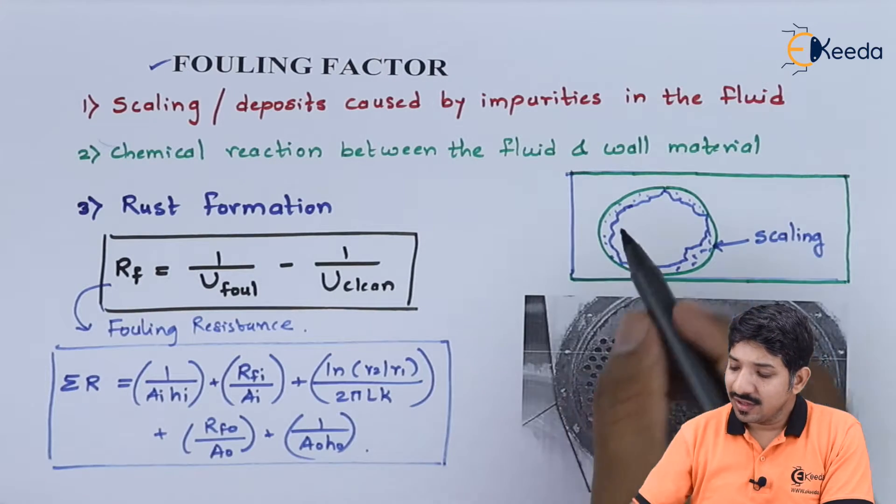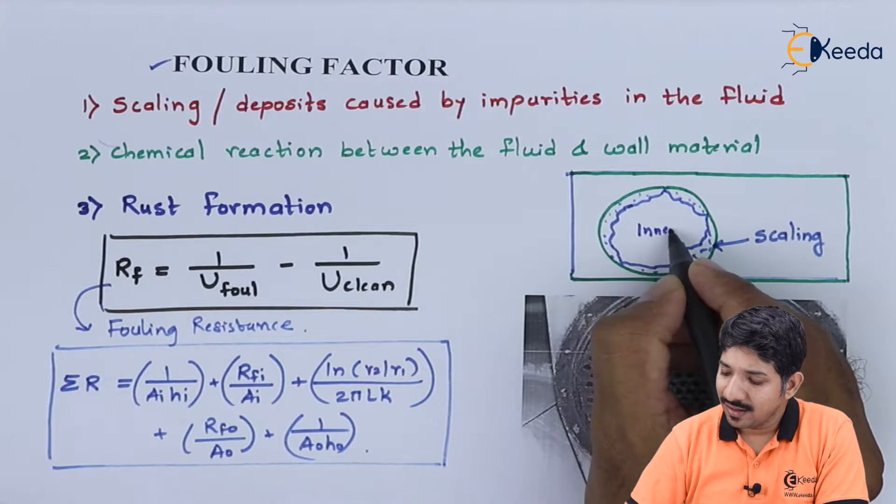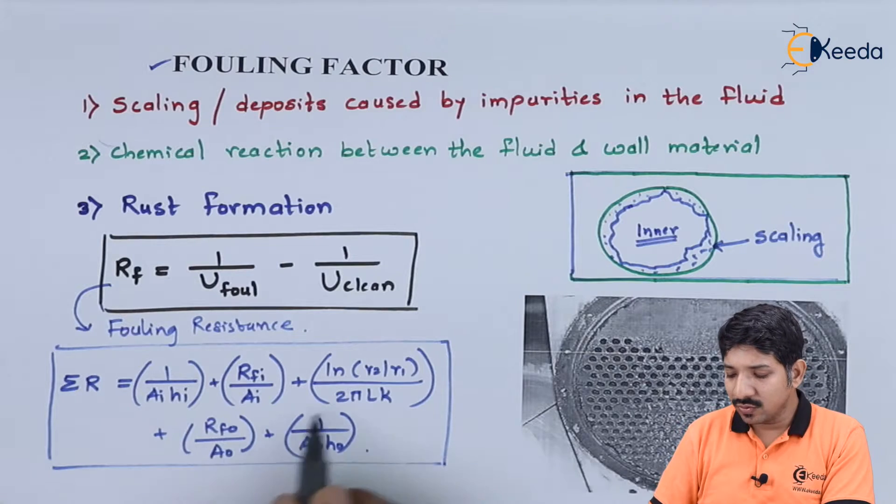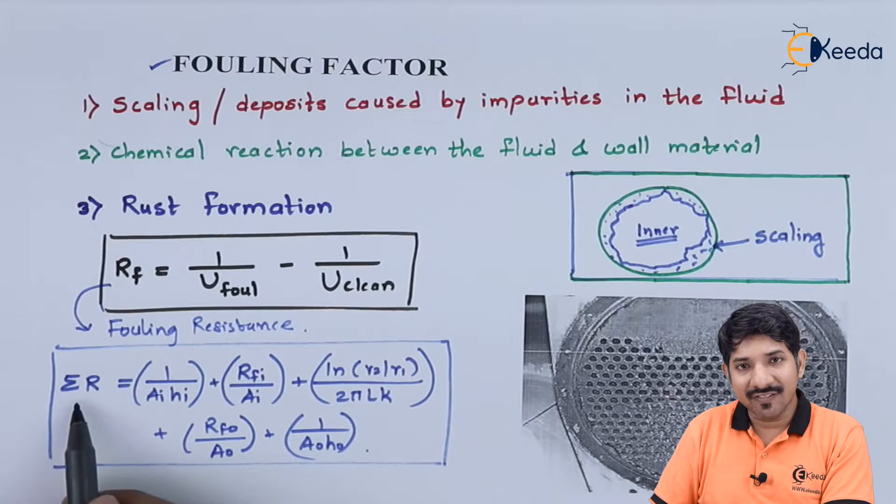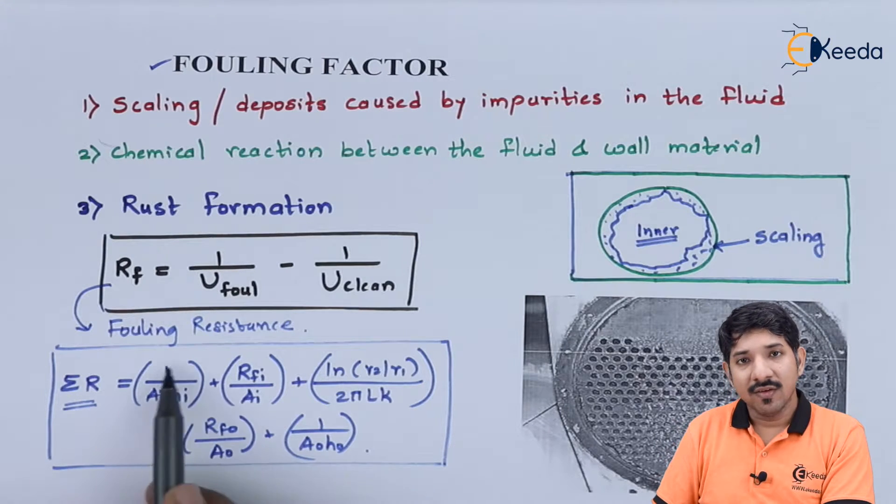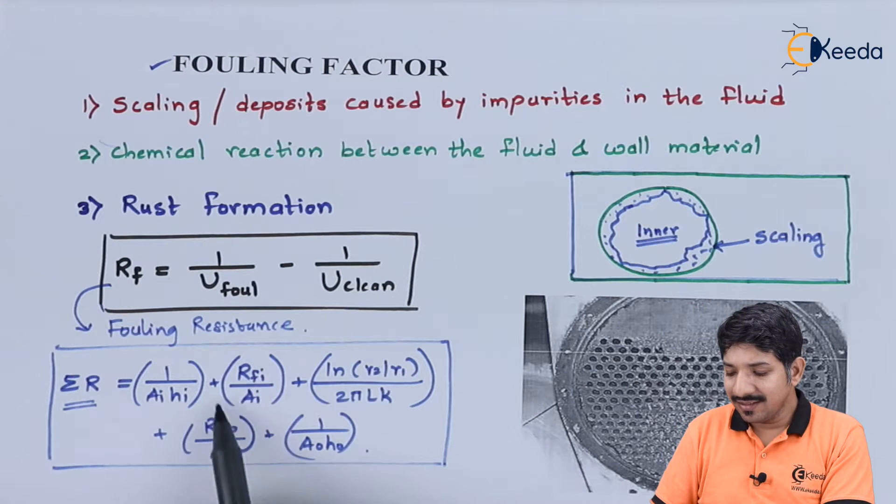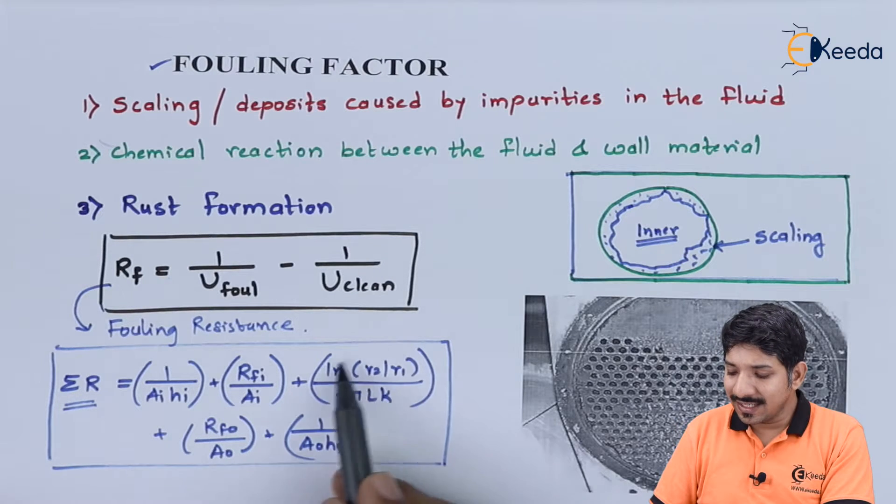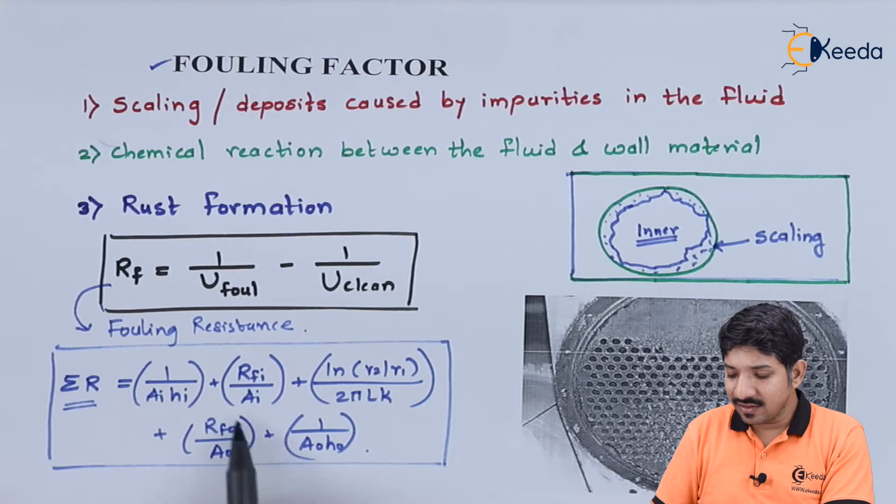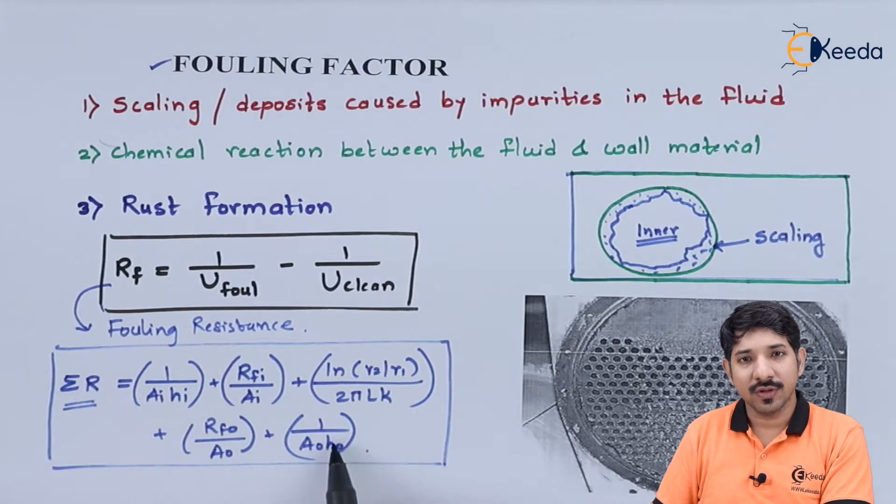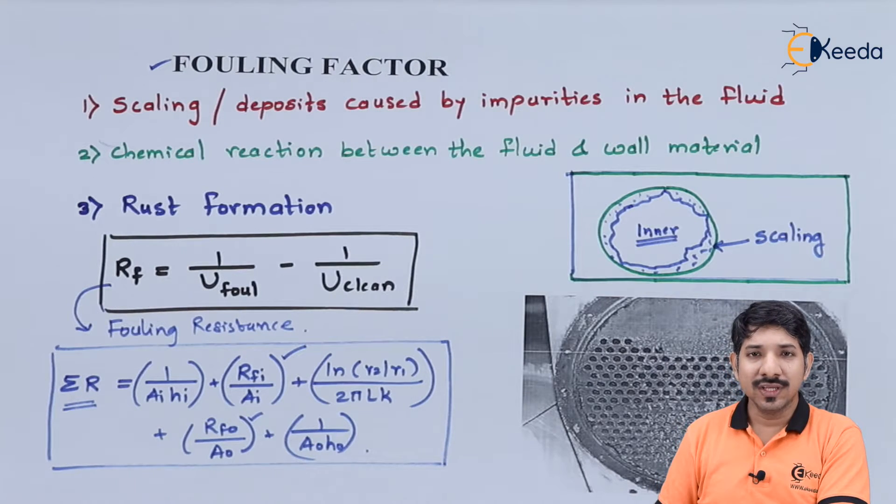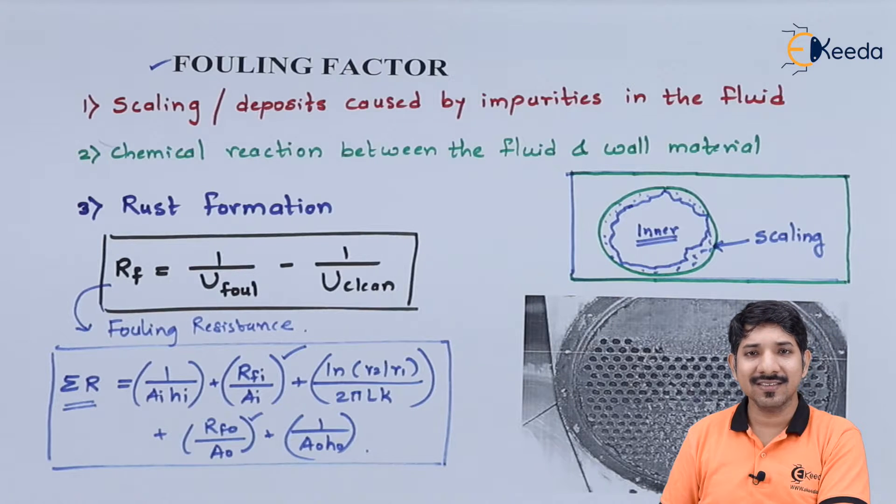If scaling occurs on both sides—the inner side of the pipe as well as the outer side—we will have to consider RFI and RFO, which need to be added to the overall resistance. The total resistance is given as 1/(AI × HI) plus the fouling resistance by the inner side, plus the conductive resistance of the wall material, then the fouling resistance of the outer side, and the convective resistance of the outer fluid. Due to increased resistance, the heat transfer rate will decrease.